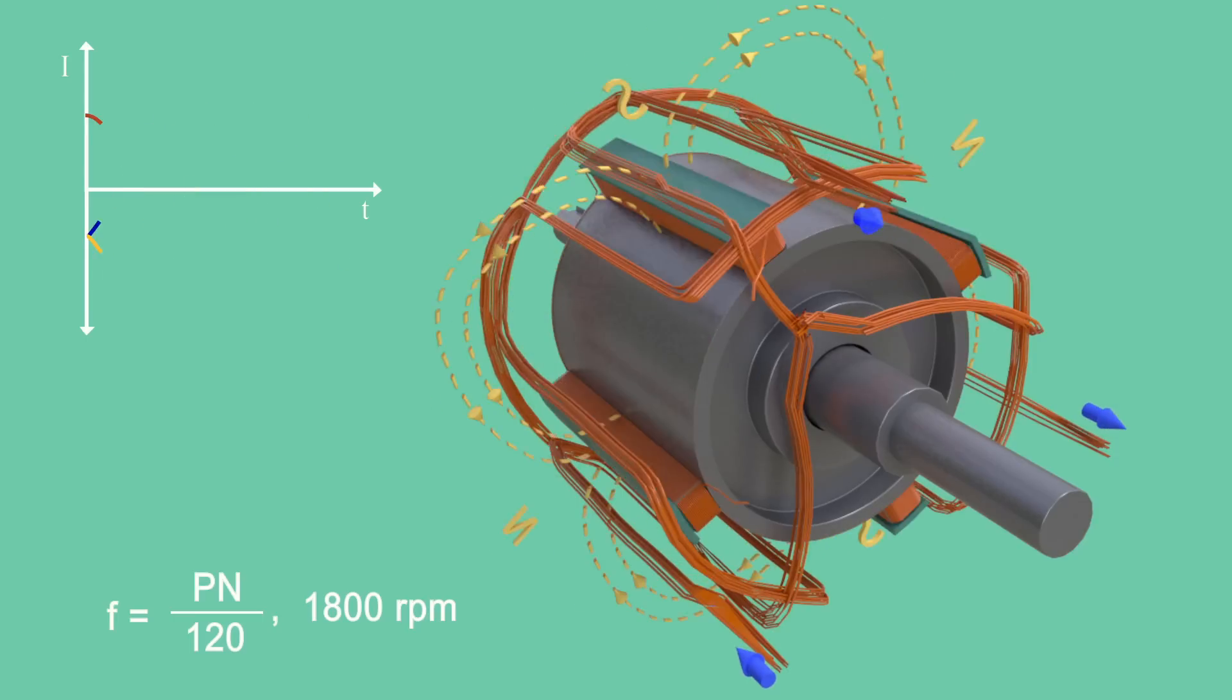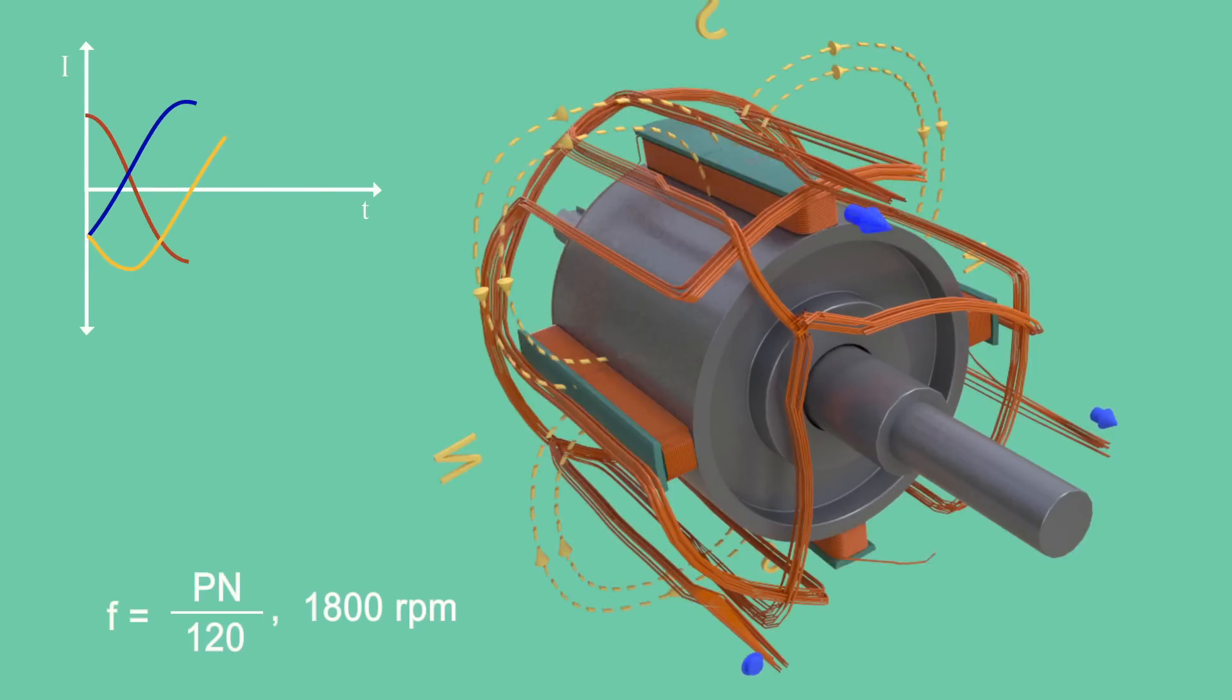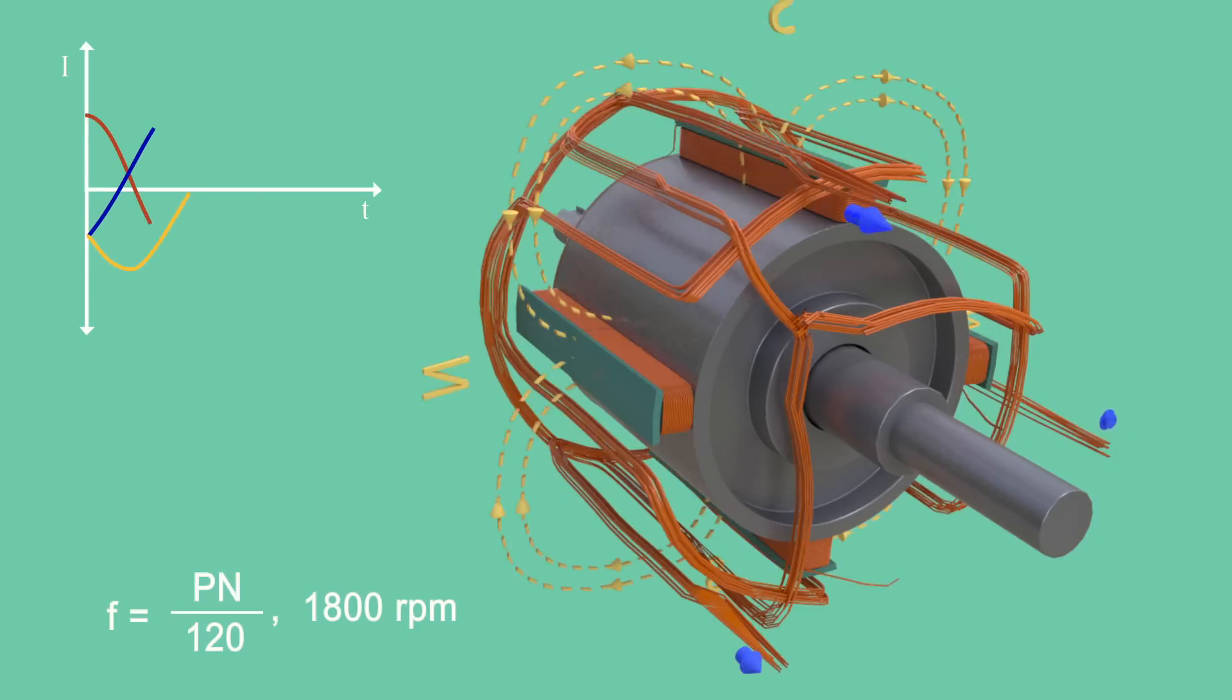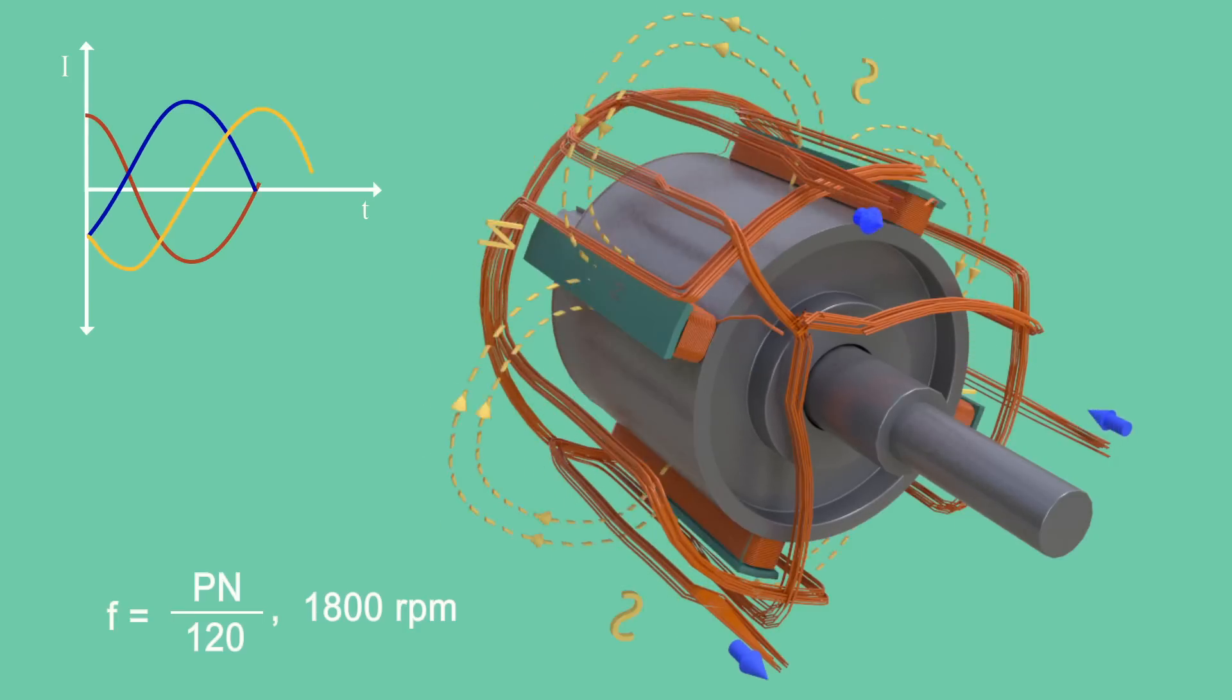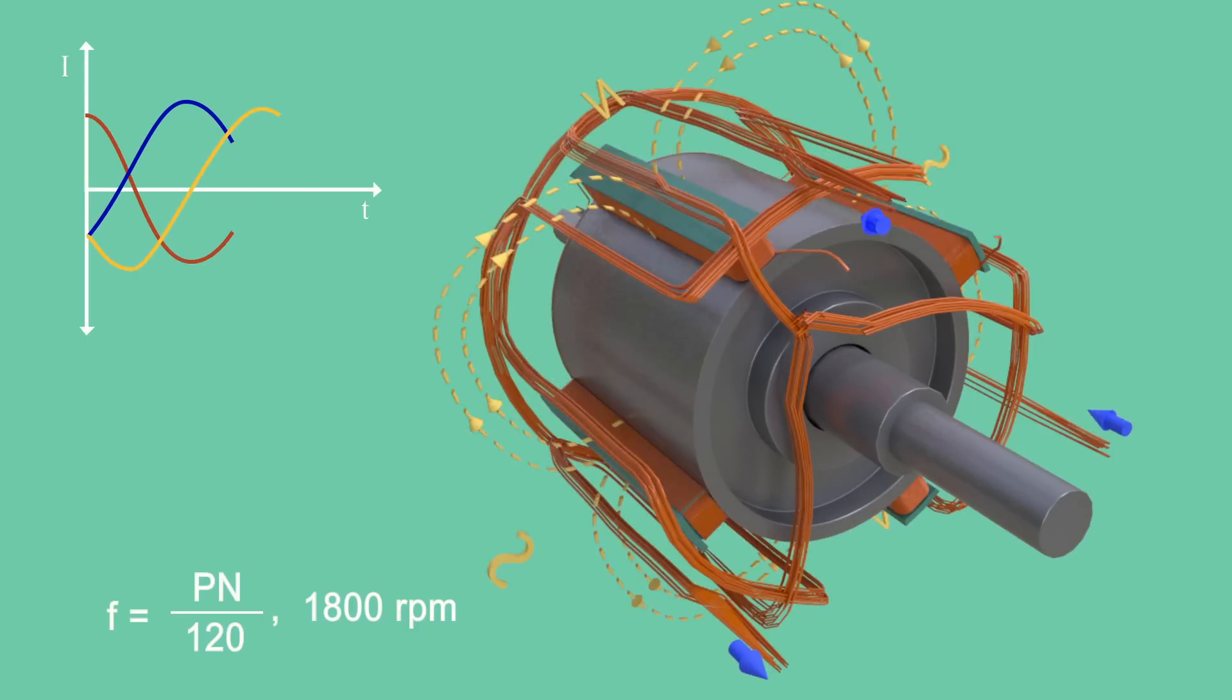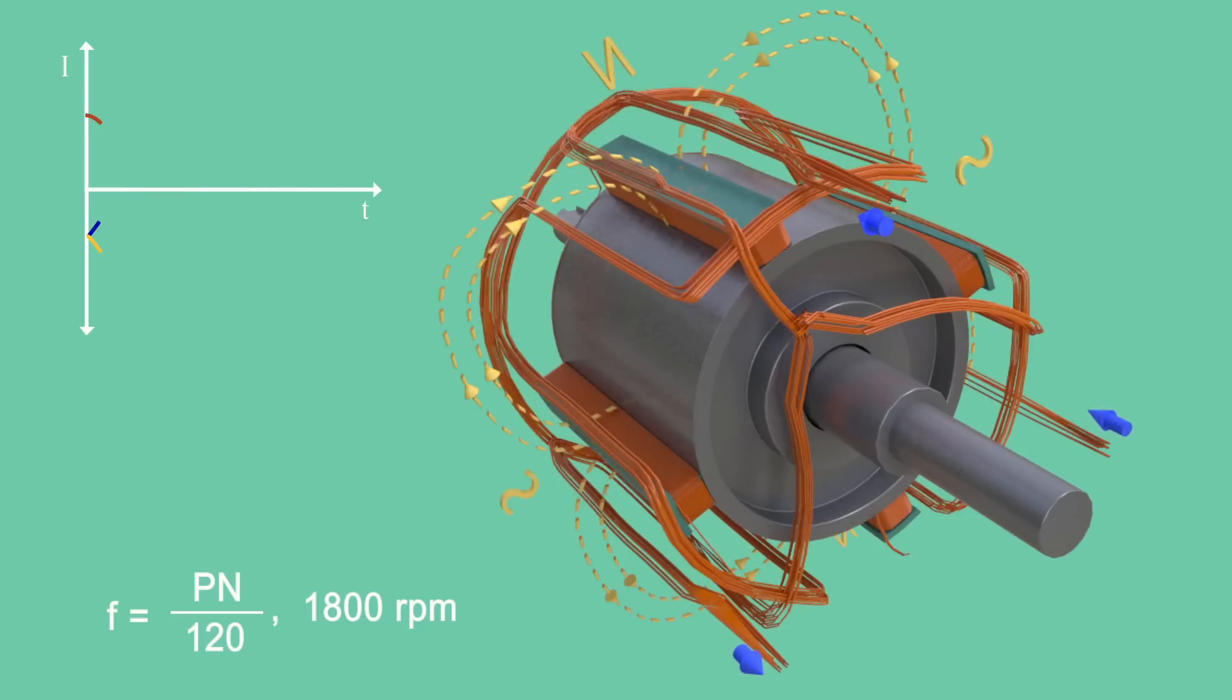Such huge RPM will induce a tremendous centrifugal force on poles of the rotor and it may fail mechanically over time. So salient pole rotors are generally having 10 to 40 poles, which demands lower RPM.